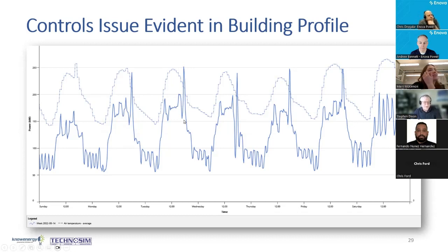This is the time when, in the summer, they would set the temperatures up, going from say 22 to 26 as a set point, allowing the temperature to rise up gently over the evening. Well, the controls didn't want to let it rise gently. They wanted to raise the temperature straight to the set point.